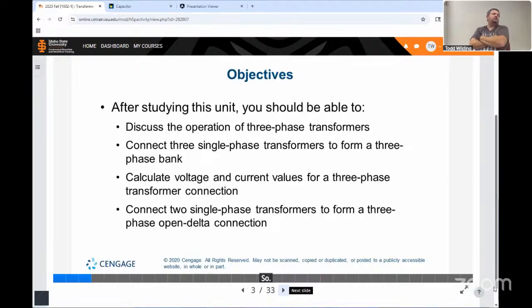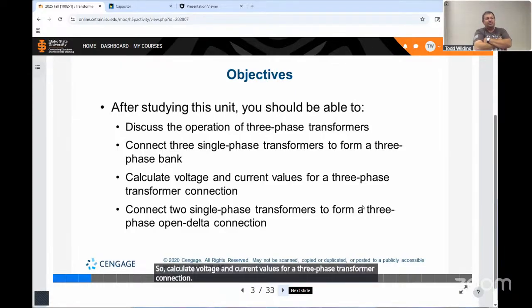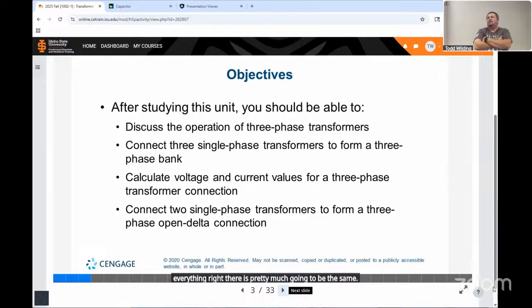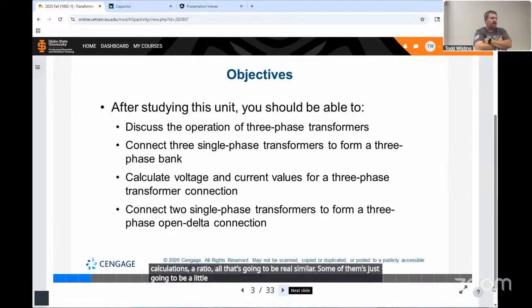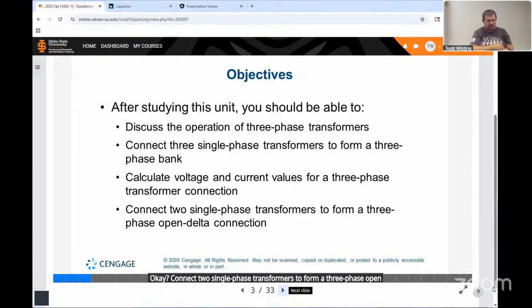So calculate voltage and current values for a three-phase transformer connection. Everything right there is pretty much going to be the same that we did 2 weeks ago with the single-phase transformers, okay? Calculations, the ratio, all that's going to be real similar. Some of them is just going to be a little bit higher, okay? Connect two single-phase transformers to form a three-phase open delta connection. Okay, we'll go over that a little bit here in this presentation as well.